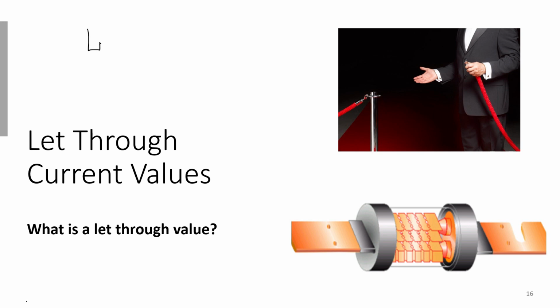So just because I have a fuse, if I have a short circuit current rating of 65,000 at this point, but he's telling me that my fuse will only allow 22,000, so don't worry about it, I can go ahead and put in a breaker or a device that's only rated at 22,000. That's kind of a misnomer. A lot of engineers will say that they can do this, and there is only one condition in which they can do so. Okay, and that is existing installations.